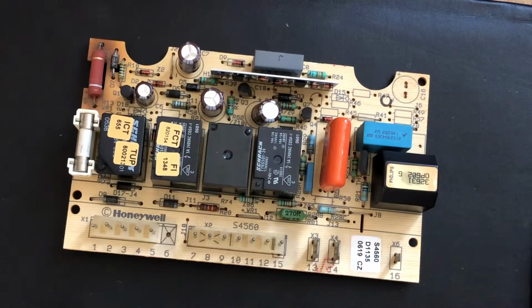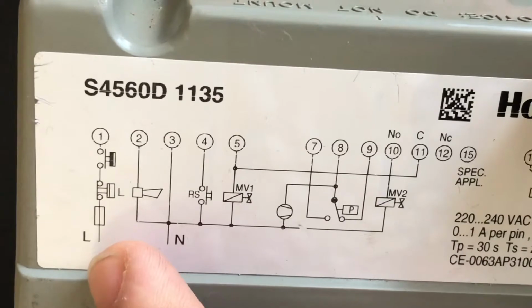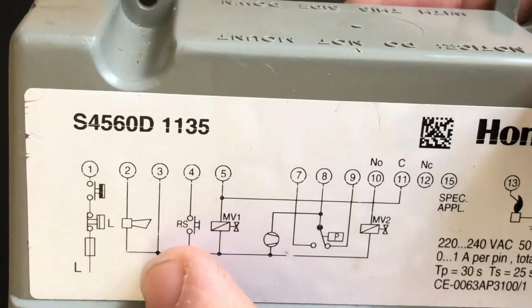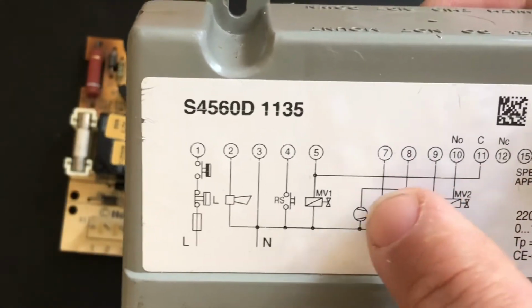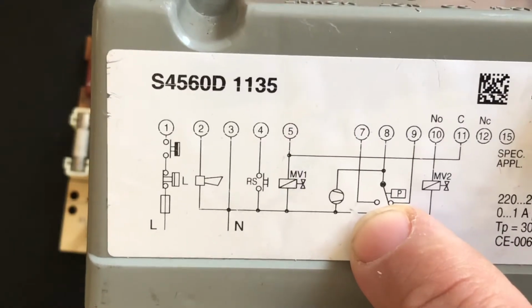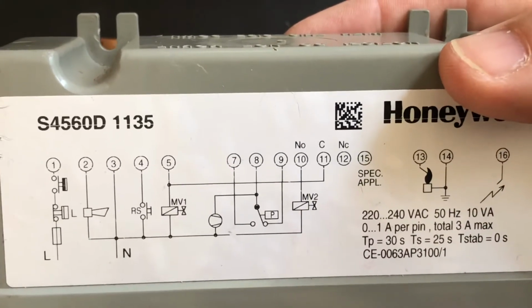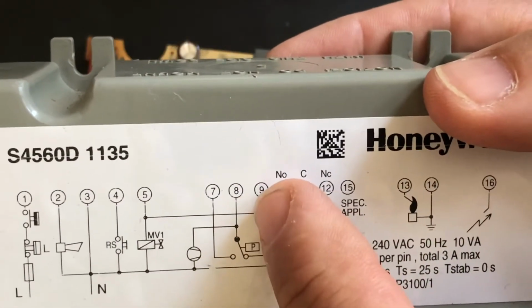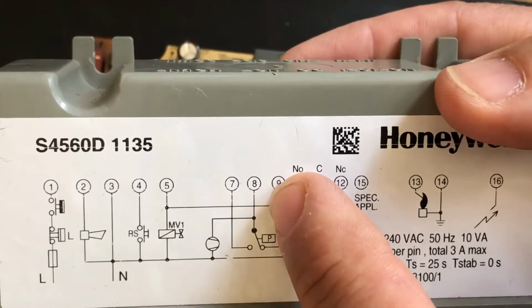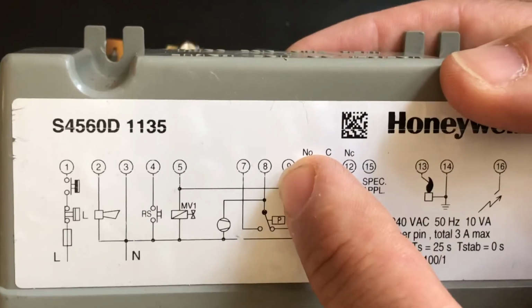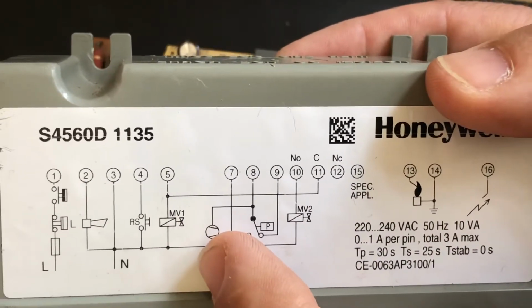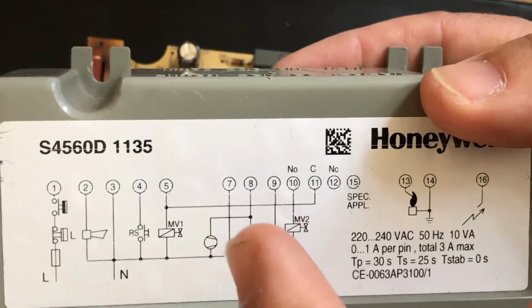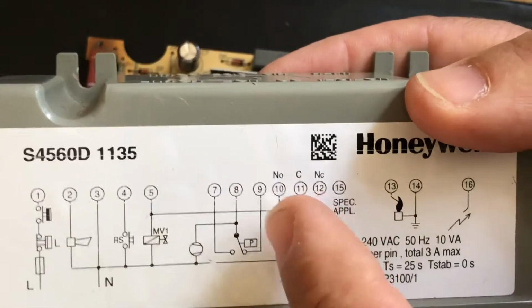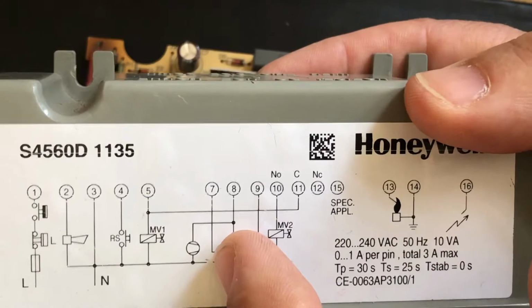So when I'm saying the story will start, if the fuse is alright and you follow the right ignition protocol, your fan must run first. If you supply power here to number 1, and you put your multimeter between 1 and the neutral, and you see number 8 and number 9, there will be a closed circuit, then the system will initiate. It's important to have 8 and 9 correctly wired onto this DPS, differential pressure switch, or fan switch, or proven switch. When the fan starts, the positive pressure or negative pressure, depending on how you put these clear tubes from this differential pressure switch, will activate the little switch, and then you will close the circuit between 8 and 7.